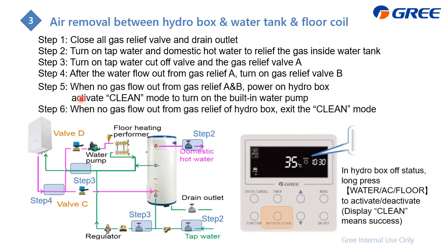As for step 5, we confirm there's no gas flow out from this A and B, then we can power on the hydro box and also activate the clean function. The method is just to press this button to activate this clean mode, and then the system will turn on the built-in water pump automatically. Turn on this one, which is to circulate the water. And then after we confirm there is no gas coming out from the gas release valve of the hydro box, then we can ensure there is no gas inside the water system. Then we can exit the clean mode.